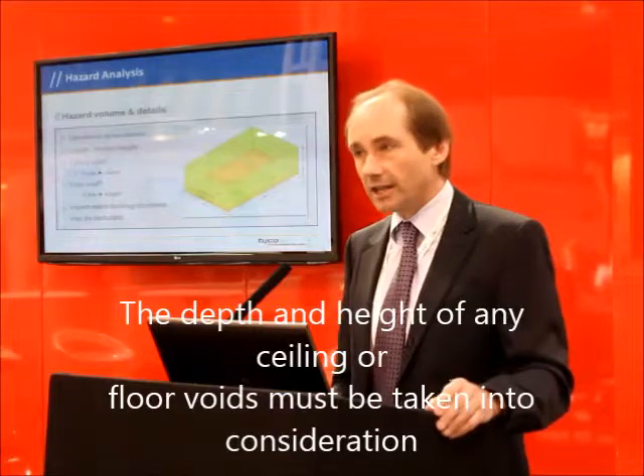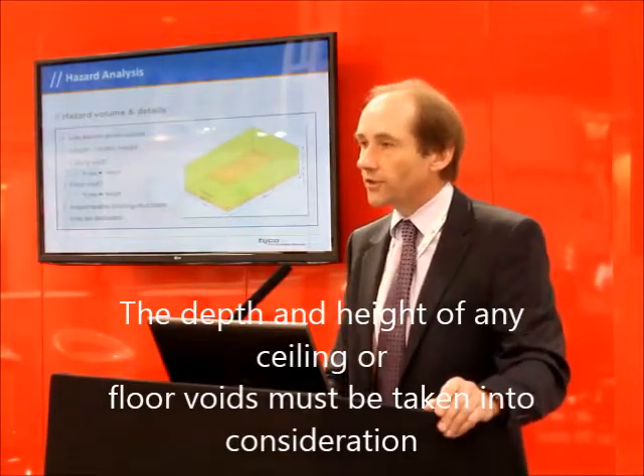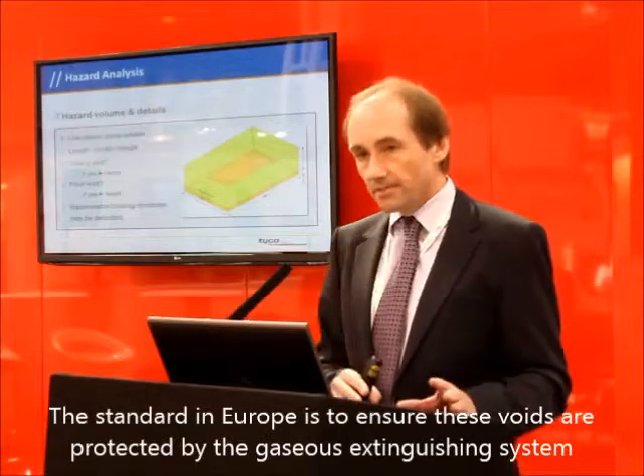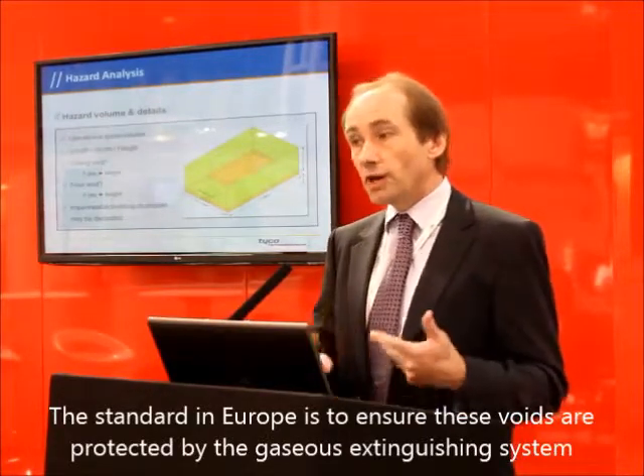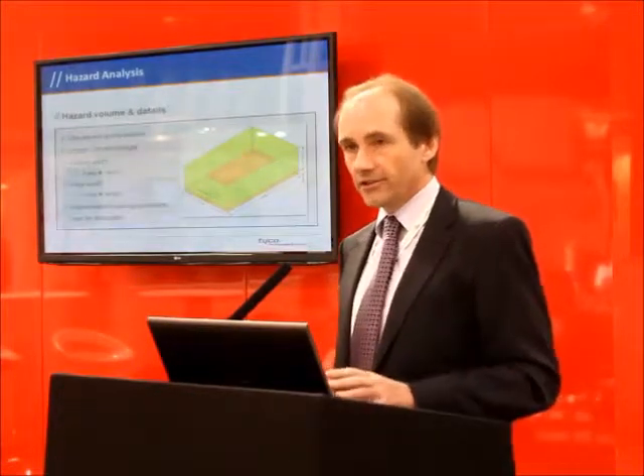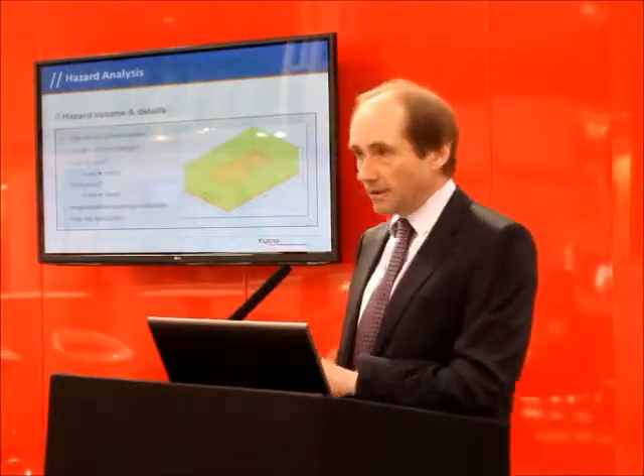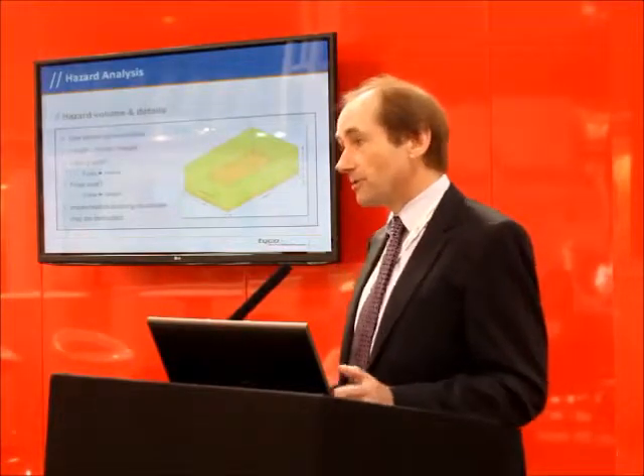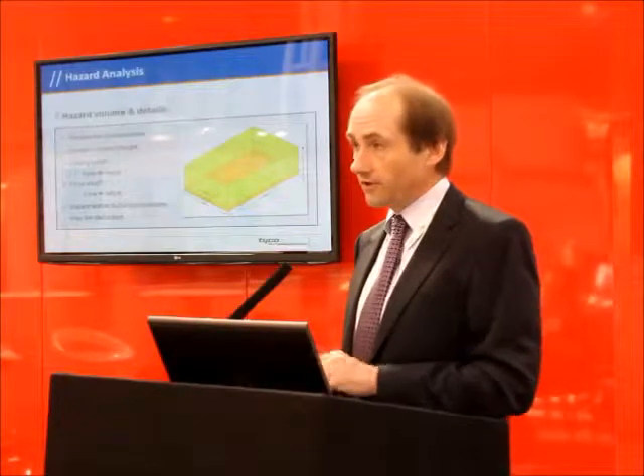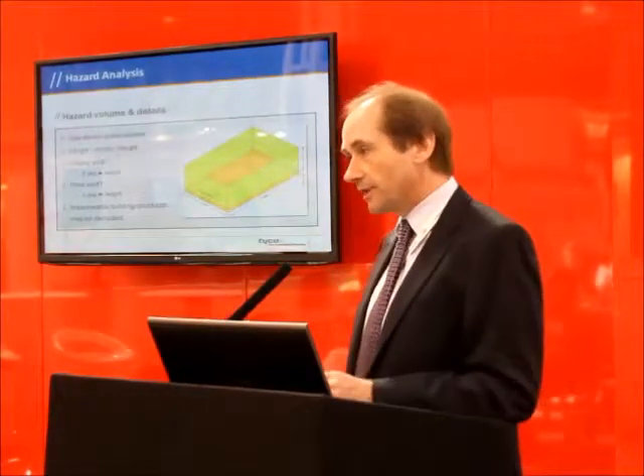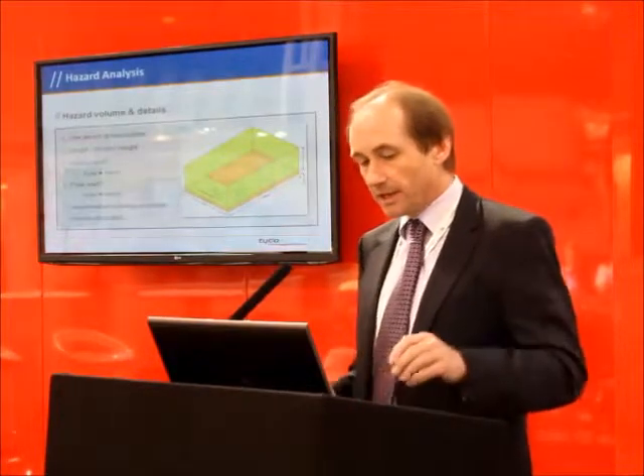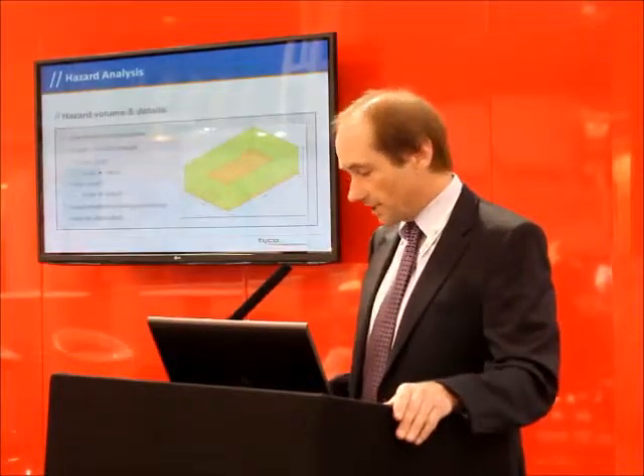We need to know the depth and height of ceiling voids and floor voids. If they're present, the standard in Europe is to protect them. If it's a US spec, sometimes it's not considered absolutely necessary to protect the ceiling void — we fundamentally disagree in Europe, but that is the US way of doing some of these things. If it's a US spec, you would need to look at the NFPA standard to determine the exact requirements.